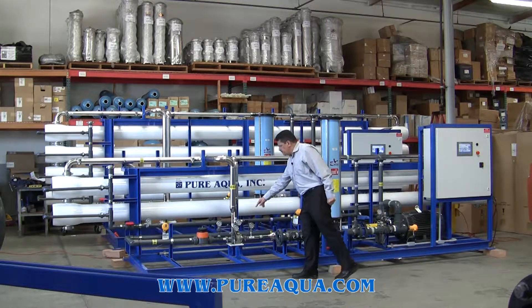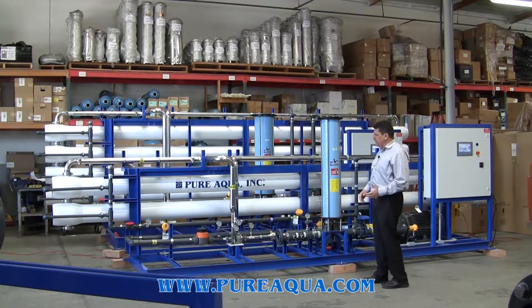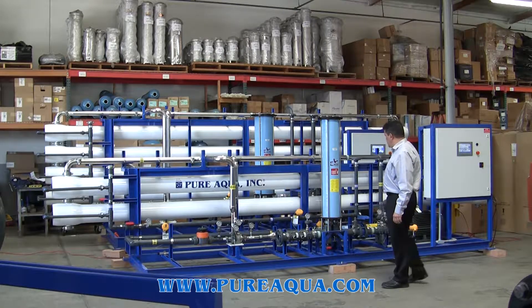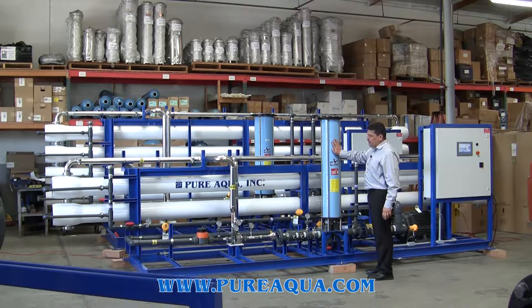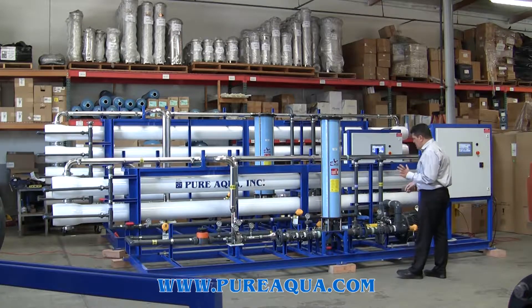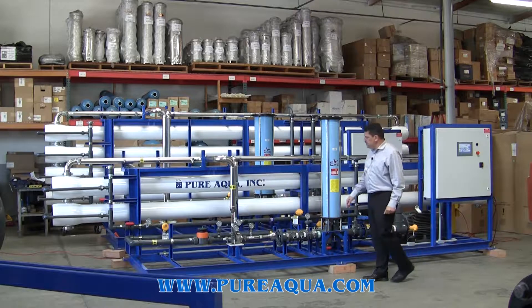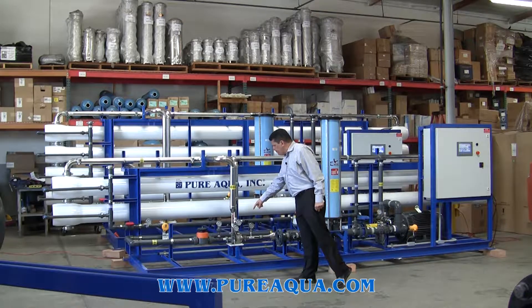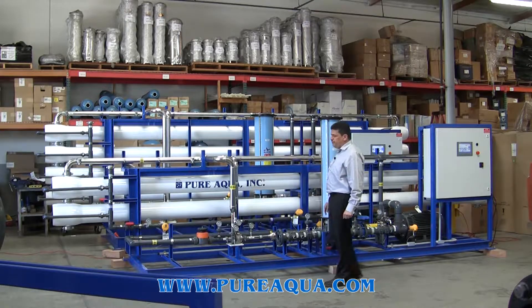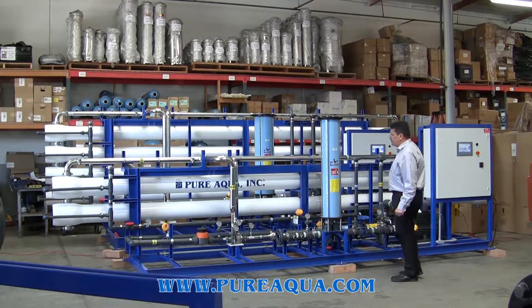This one here has a high pressure switch and a low pressure switch, both made of duplex stainless steel to resist corrosion from seawater. We have a non-metallic fiberglass filter at 5 microns. The pumps are made by Fedco and are super duplex stainless steel. The energy recovery device, also made by Fedco, saves about 35 to 40% of power consumption.